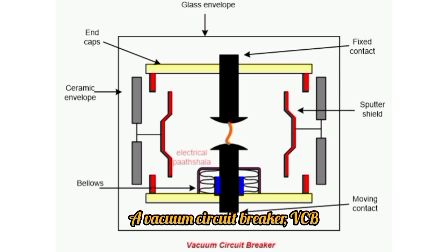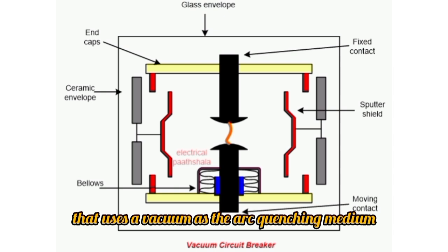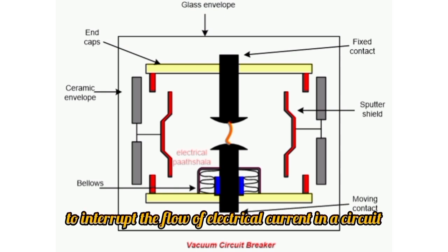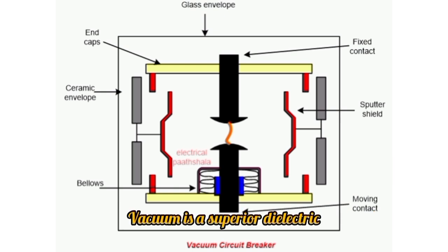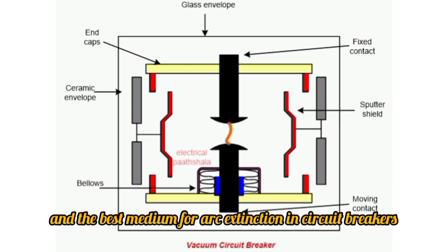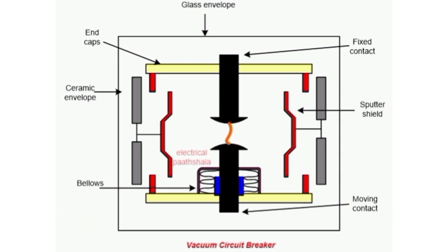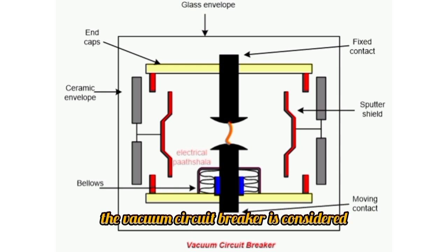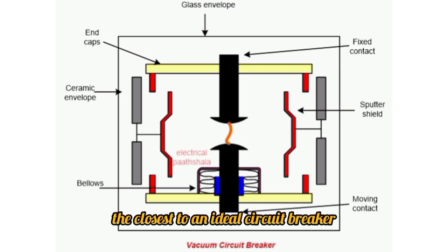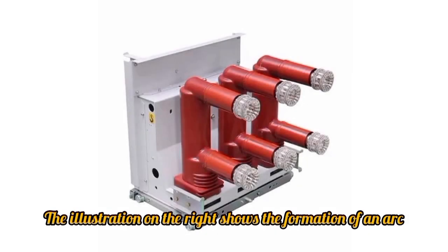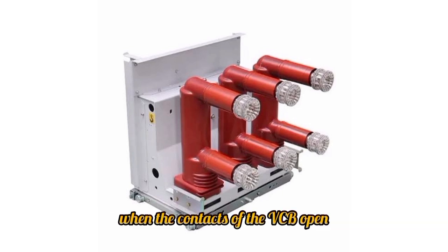A vacuum circuit breaker, VCB, is a type of circuit breaker that uses a vacuum as the arc quenching medium to interrupt the flow of electrical current in a circuit. Vacuum is a superior dielectric and the best medium for arc extinction in circuit breakers. For medium voltage, for example up to 38 kV, the vacuum circuit breaker is considered the closest to an ideal circuit breaker. The illustration on the right shows the formation of an arc when the contacts of the VCB open.